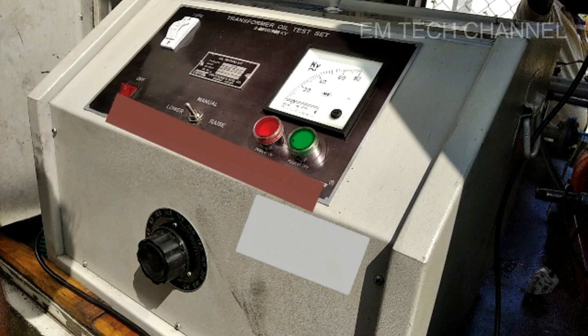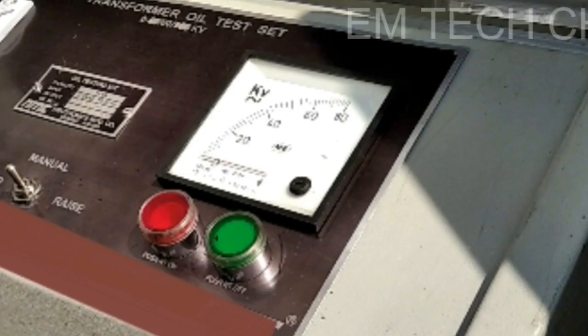The red and green buttons seen here act as both switch and indicator. When the red color switch HT on is pressed, HT supply will be energized, which can be seen from the red indication. The green button is used as a switch to switch off the HT supply, and if the breakdown occurs, it will output green indication. The toggle switch, which you see here, is a 3-position toggle switch, which when shifted to left decreases the HT voltage, and when shifted to rightmost increases the voltage, and when left in the middle position, the voltage will remain constant. You can see the voltmeter that ranges from 0 up to 80 kV.